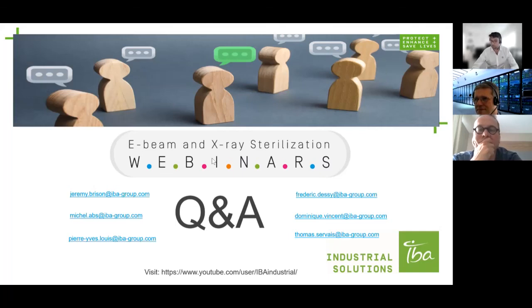It depends a lot on the product, the dose, the distance to the product. What kind of DUR do we need? For example, simply changing the overscan on the product will have a big impact. Will it be a low density product or high density? These numbers can vary quite a lot, but we can really nail them down very precisely, more precisely than ever. We have a very complex model now which calculates all the process data and then converts it to a business case where we take the local labor cost into account, local cost of electricity, importing fees, et cetera. So I would say connect to us and let's take 15 minutes or half an hour to make something precise. I don't want to give a rough number here, which wouldn't be relevant or significant. I'm sorry about that. I know I always get these questions, but it's really difficult to answer them live without having all the data.